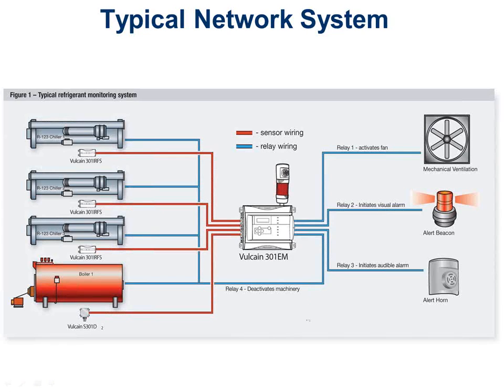If I have multiple things going on, I don't necessarily have to have multiple control systems, right? I can have one control system measuring multiple things. Now, in general, I'm not going to have the chiller and the boiler in the same room, right? But I might have them on the same control system, if you will. In this case, I'm monitoring 3 refrigerant sensors for chillers. I'm also measuring sensors for the boiler, which is probably a carbon monoxide sensor or a methane sensor, depending on what this boiler is doing. And it could all be going to one control panel that's doing all my fans and alarms and horns for me. So I could network these things together if I want to.